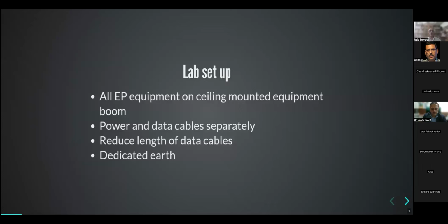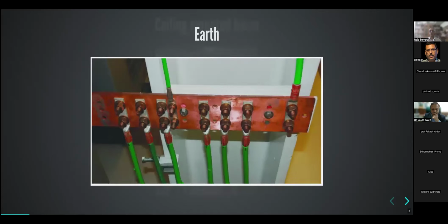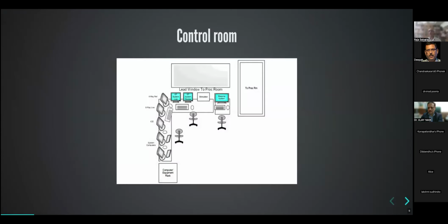Now, the cable from the patient that goes to the amplifier is still carrying analog signals, and from the amplifier it gets digitized. So try to reduce the length of this part of the cable. The amplifier should be as close to the patient as possible, because that is where a lot of the noise will leak in. And try to have a good earthing setup, a dedicated earth for the lab, and all equipment should be earthed to this, since that is an important source of noise.